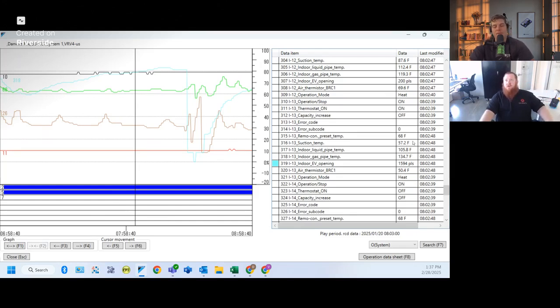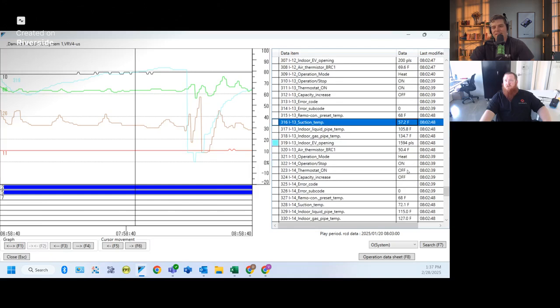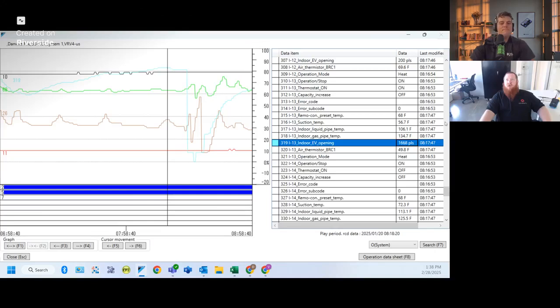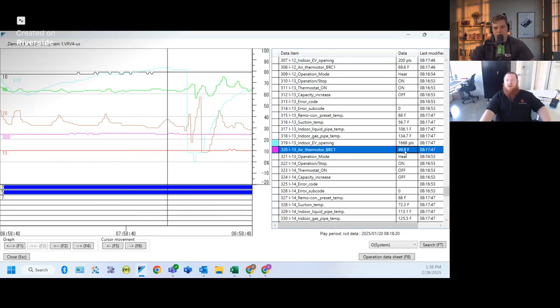But our return temperature is in the gutter. So this space looks really cold. It's a little chilly. 50 degrees is a little cold. So this unit is trying to heat the best it can. That expansion valve is going basically full open and trying to maintain that, but it just can't do it. Our space temperature actually dropped in that time.